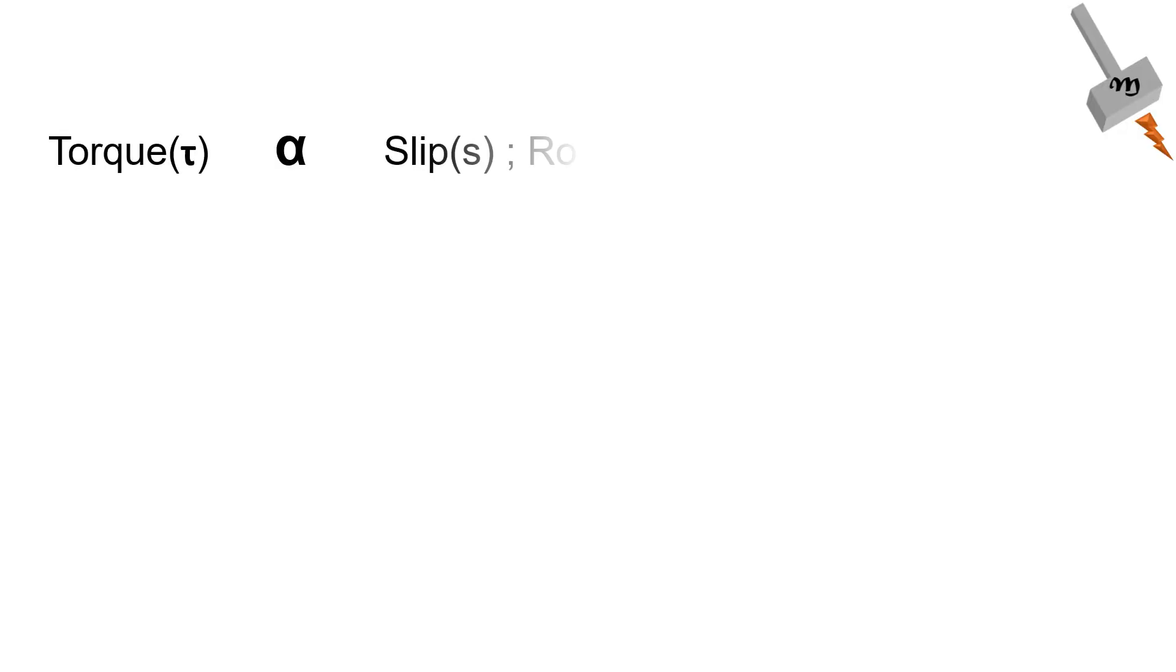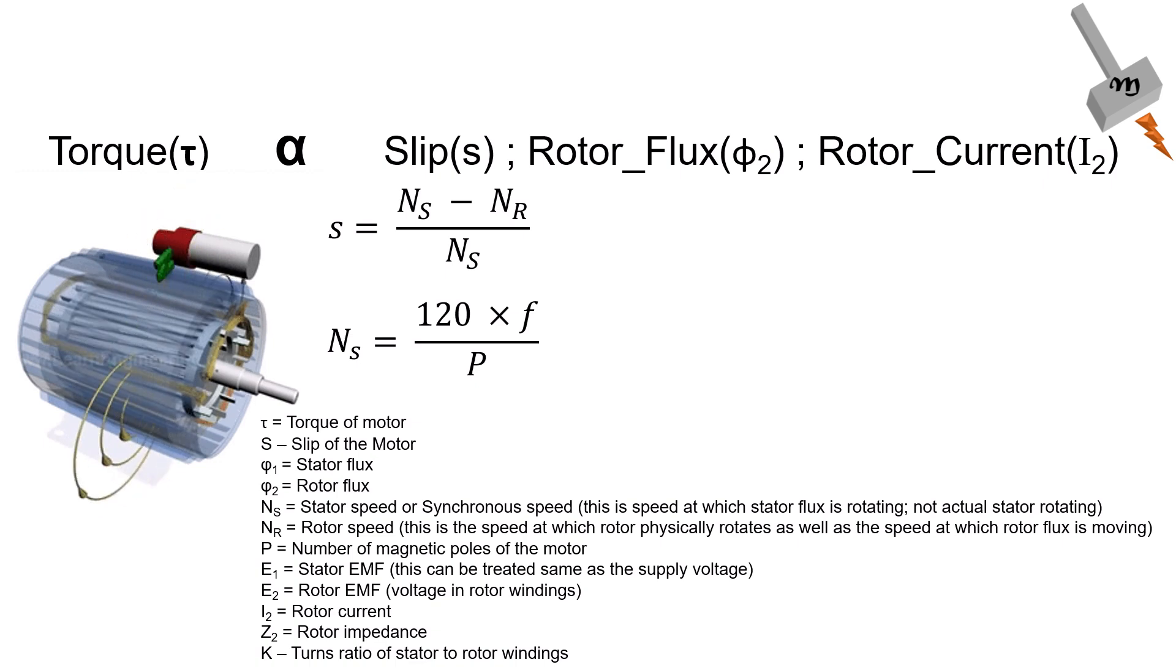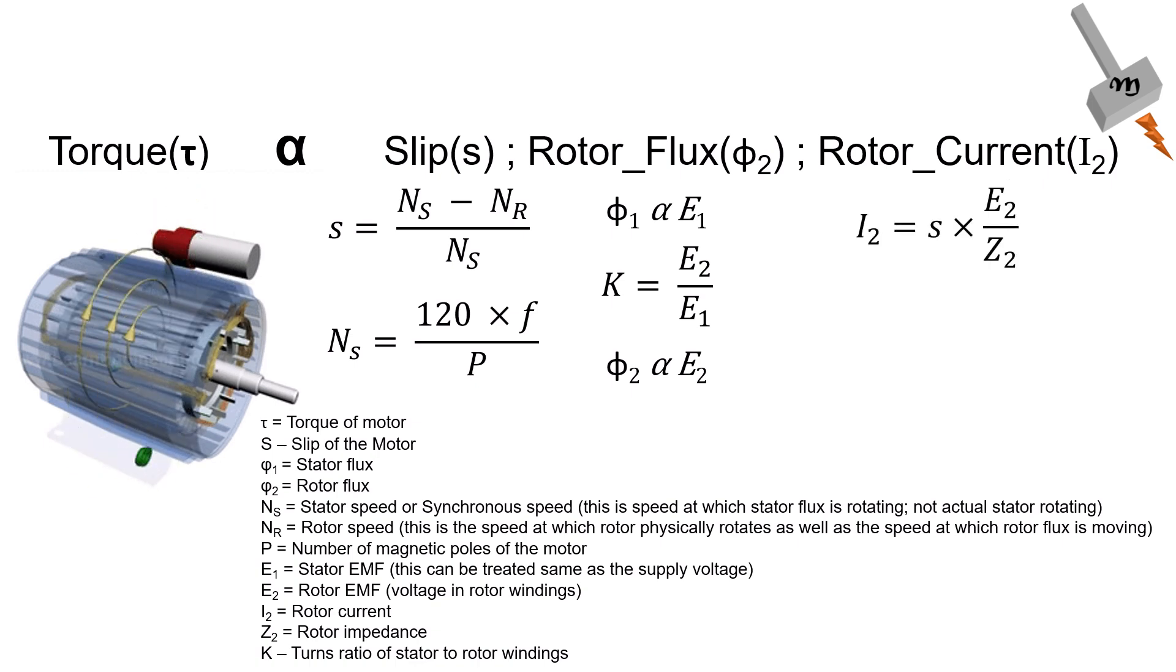Torque is proportional to slip, rotor flux, and rotor current. Slip of a motor is the relative difference between synchronous speed, which depends on the supply frequency and rotor speed, and is responsible for linking stator flux with the rotor windings, thus creating the rotor flux, which is responsible for magnetizing the rotor and generation of rotor EMF, which in turn causes the rotor current to flow in the windings, thus creating the torque in the rotor shaft.